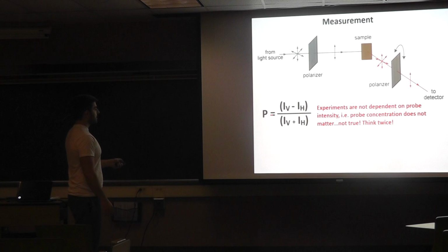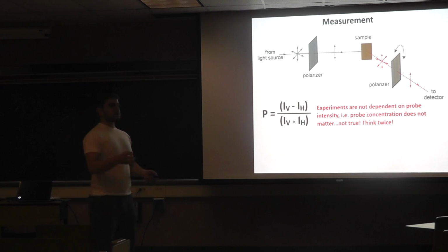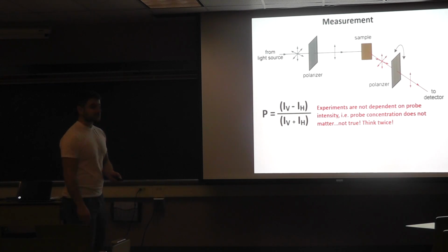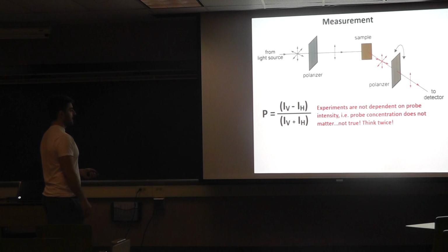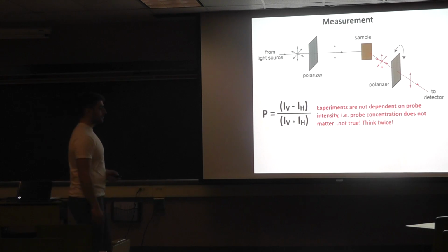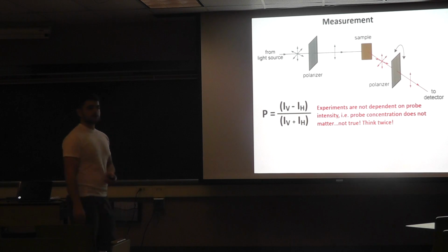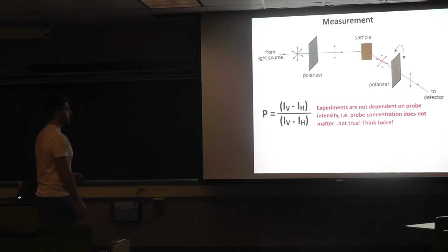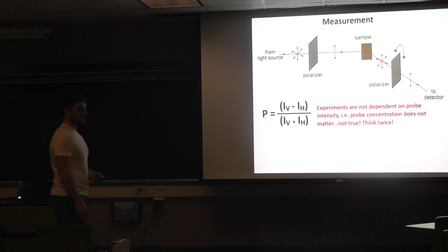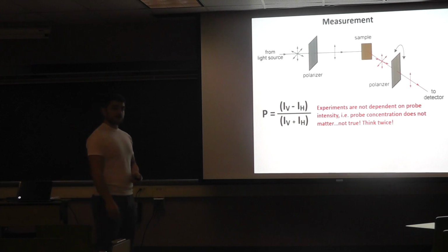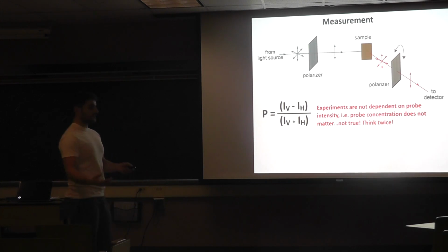It is not actually measured in polarization, it's measured in millipolarization. These values technically can go up to 1,000 millipolarization, but experimentally people have seen that it doesn't really go more than 500. If it is going more than 500, there might be some problem either with the equipment, your sample preparation, or the way that you blank your machine.